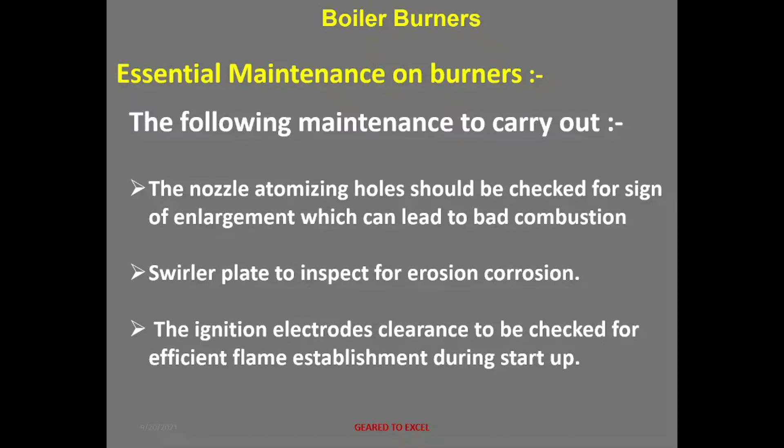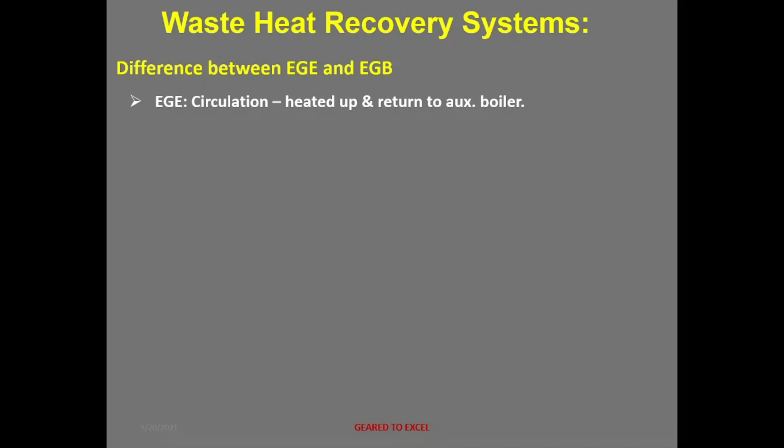Waste heat recovery system — difference between EGE (Exhaust Gas Economizer) and Exhaust Gas Boiler (EGB): the EGE circulates water, heats it up, and returns it to the aux. boiler. The EGB has steam storage capacity and a full set of mountings. Pinch point is also introduced as a key concept.